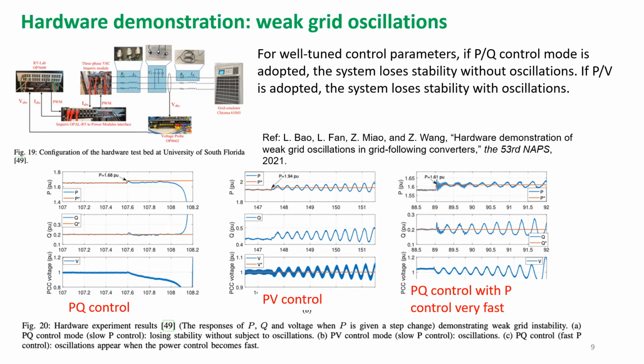In the first figure on the left, the inverter is in PQ control mode, which regulates real power and reactive power. There's no plant level control, and the voltage collapses at a certain level when P is ramping up. In the second one, we see oscillation because we switch the reactive power control to voltage control. In the third one, we again play with parameters and see that even with PQ control, when we make the P control very fast, oscillation can happen.